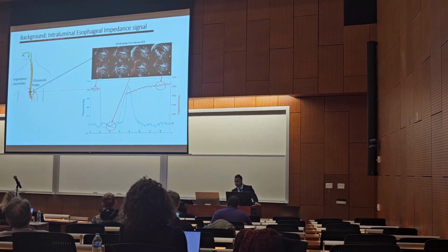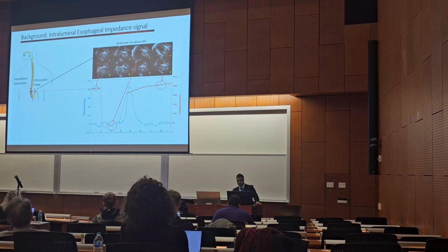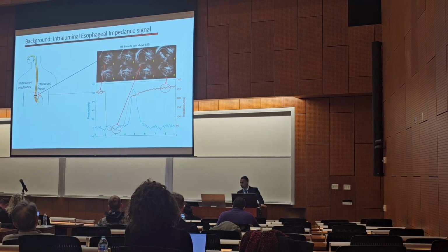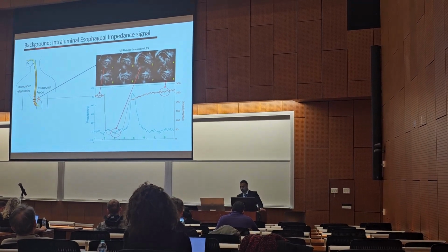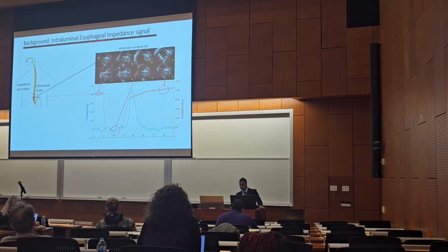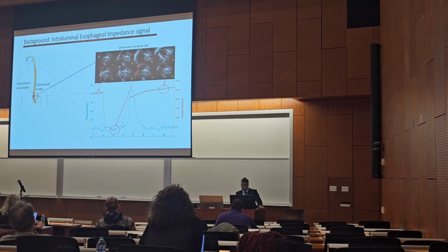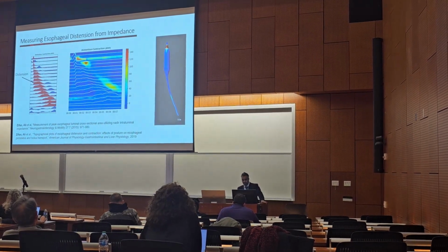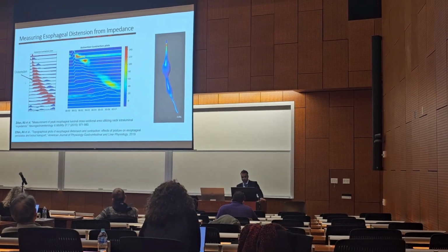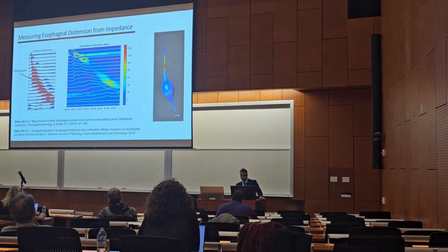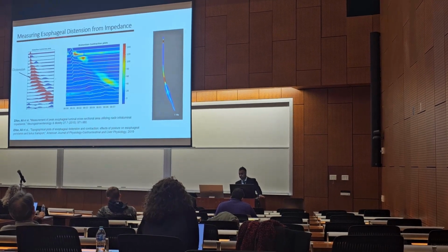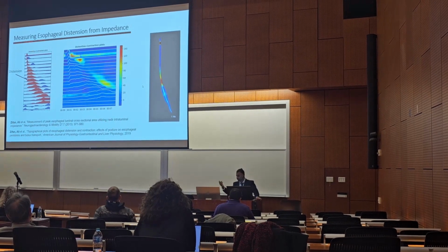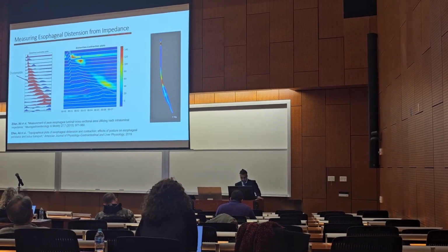If you do simultaneous ultrasound with manometry, and you see the impedance channel shown in orange, you see the dilation of the esophagus, let's say at a certain level above the lower sphincter. It coincides with the drop in impedance. So you can use laws of physics to estimate distension from impedance, and that's what we did around a decade ago. We introduced different methods and visualizations for, for the first time, actually visualizing distension, shown in red, and pressure in blue. We also introduced a cylindrical form of pressure so the physician can see the pressure overlaid on the distension.